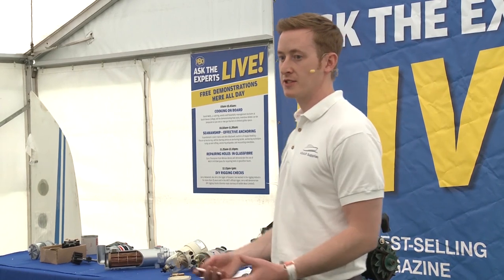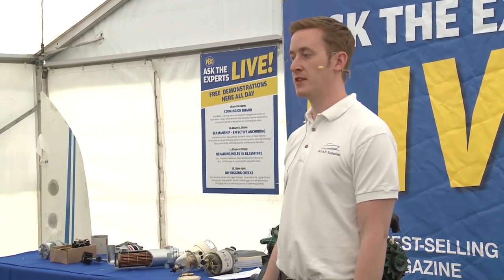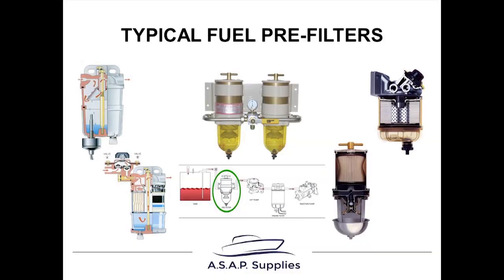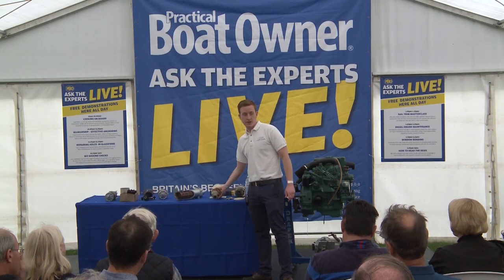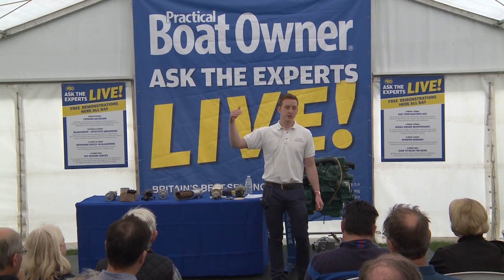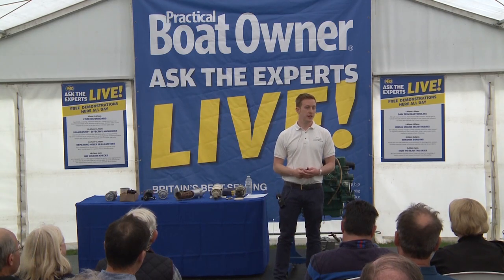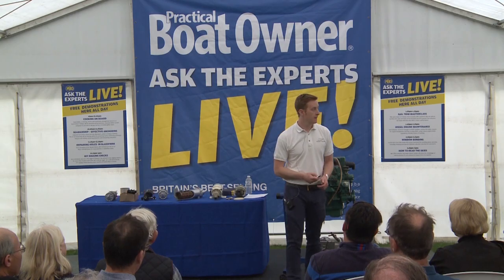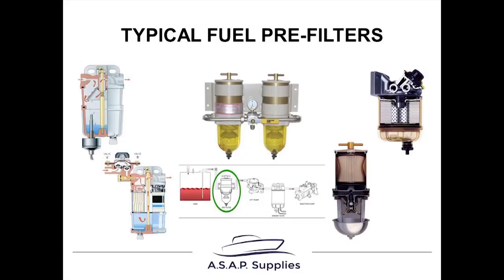So all that together means you need to be more aware of the diesel system itself. The first component is a typical pre-filter, some people call it a water separator. It's basically something like this, and it's designed almost like a strainer. It's the first filter in the system - the diesel comes through and it takes out the large particles and the water. There's lots of different options, and they've changed over the years - depending on the horsepower of the engine, the age of the engine, and things like that, determines which one you'd like.